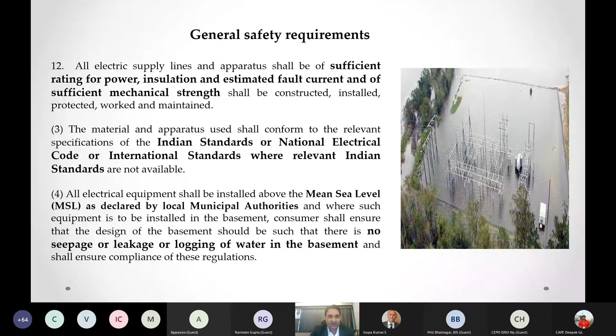Another requirement concerns mean sea level. If you see the diagram, the whole substation is filled with water, as there is no proper water discharging system. So the installation shall be installed above the mean sea level. If the mean sea level is not declared, then the mean sea level declared by the local municipal authority has to be followed.